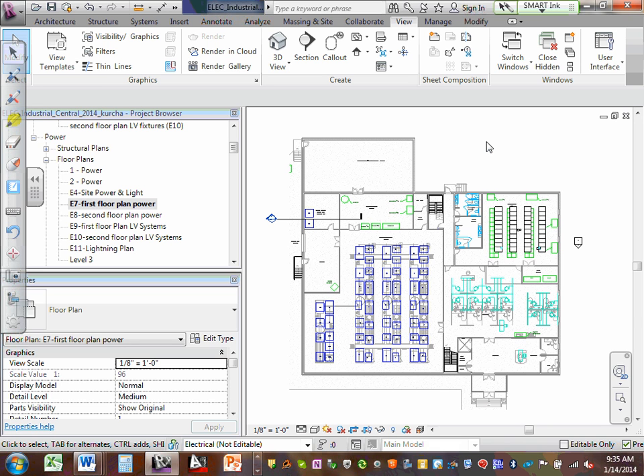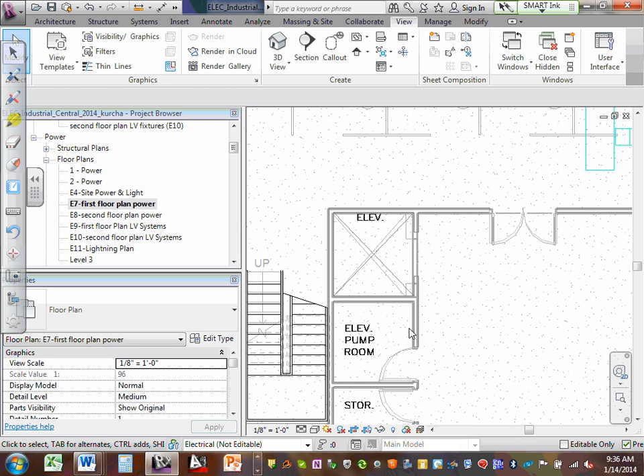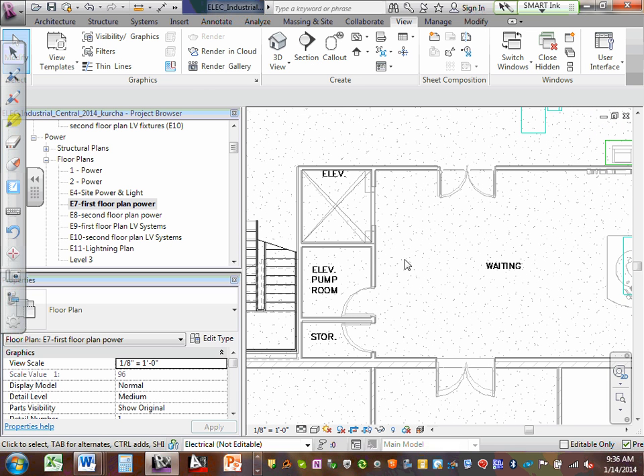Okay, so let's go ahead and design a fire alarm system. There are some pretty basic things that you do need to provide in this design that are a function of things that exist in this project, that exist in this building. One, you've got an elevator, right? Okay. The elevator code requires that if that elevator has 2 or more stops, it must have what's called recall.